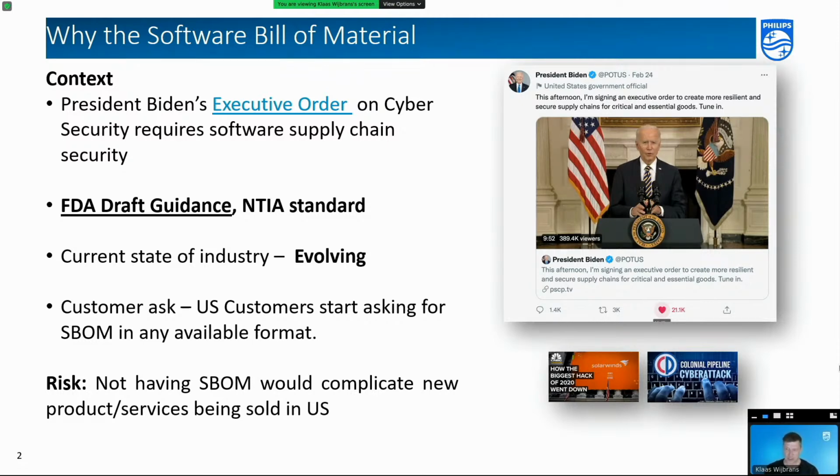However, the one that apparently seems to get the greatest focus in a lot of the industry is the software bill of materials. It's not totally new, because already in 2018 there was an FDA draft guidance for medical equipment, which was essentially more an announcement that something would be coming up on a so-called cybersecurity bill of materials, and that one would cover both the software bill of materials and associated hardware, which was security related.